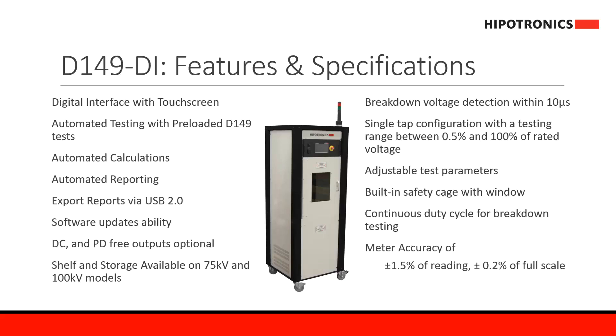The 75kV and 100kV versions have a shelf available to store accessories used during the test. This system's breakdown voltage detection is within 10 microseconds, and one of the main new features of the D149 DI series is a single-tap configuration that allows the operator to test from 0.5% to 100% of the rated voltage.